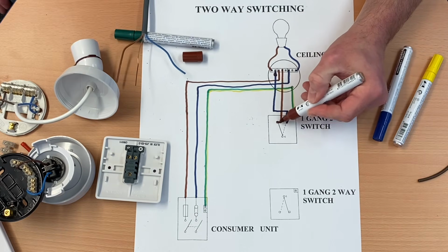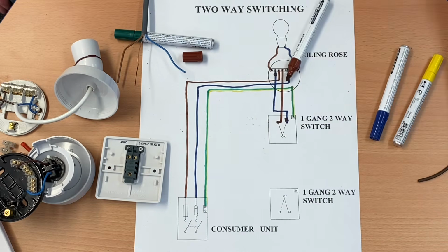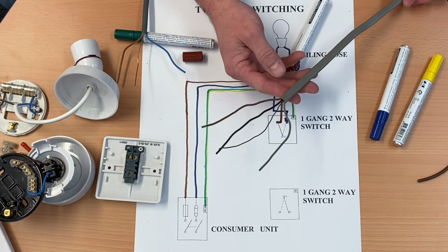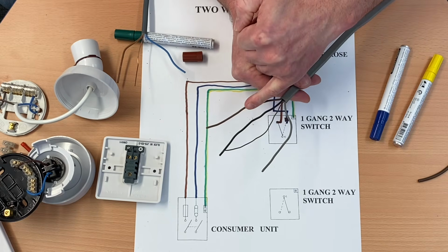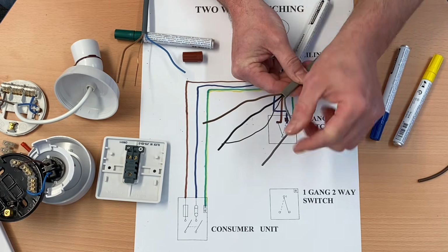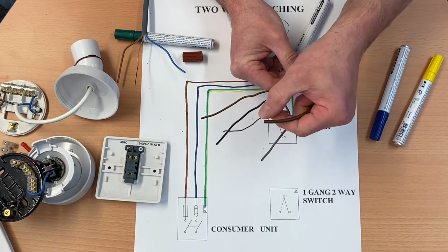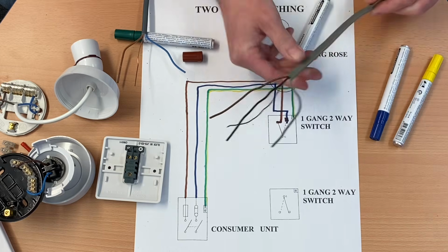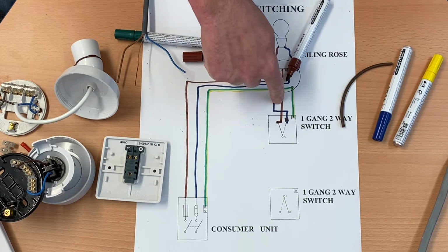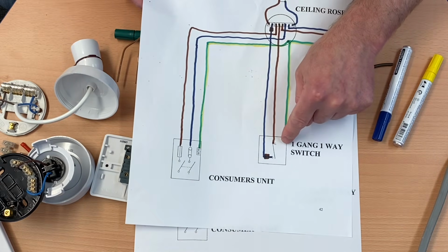So now we've got to work out what cable links our 2 two-way switches together. And that's going to be this one here. This is our 3-core and CPC. And again, you can see only one of the conductors is brown. We've got black and grey. And the 2 that we are using for switching line conductors, being grey and black, will need identifying with brown sleeving. And of course, green and yellow sleeving on our CPC. So if we have this cable coming down here as we would in a one-way switch, so exactly what we've got here, we had a blue, a brown and a green and yellow coming down to a one-way switch.